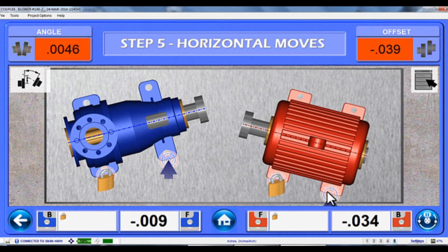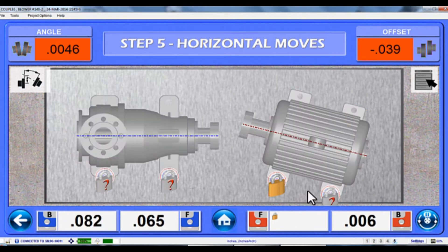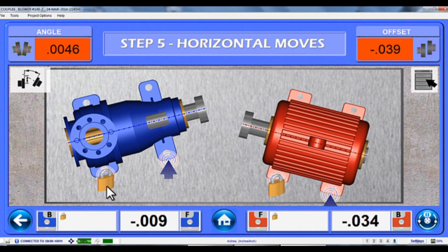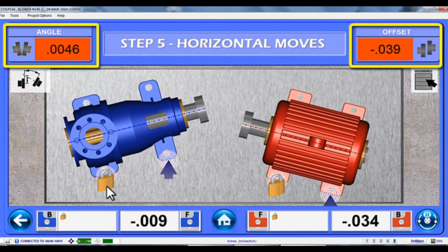You can use any combination of Motor and Pump feet to see which of the Move values will align the motor without having to move the motor in the direction it is bolt bound. Once you have the combination that works, you can use the Live Display values and Motor Graphics to align the motor.